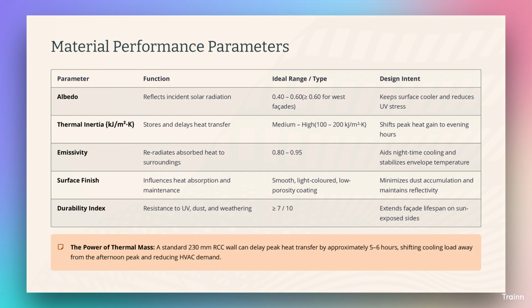The power of thermal mass. A standard 230 mm RCC wall can delay peak heat transfer by approximately 5 to 6 hours, shifting cooling load away from the afternoon peak and reducing HVAC demand.